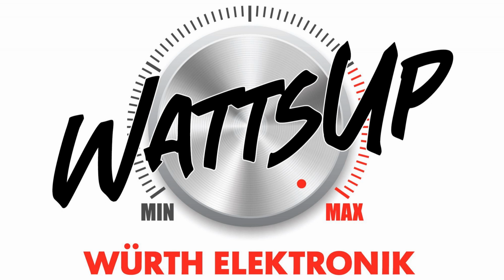We find out that as soon as we take out this potting material, look what happens with the same construction, just the same transformer without potting material. We passed the EMC test. So because of that, we decided not to use varnish or potting material in the transformer, because that may also cause some negative EMI effects, some noises.